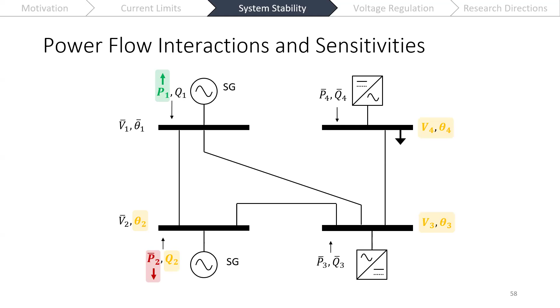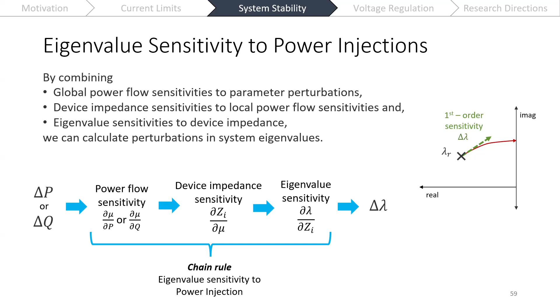What we can do then is calculate what those perturbations in our power flow would be in response to a change in the power injected at some other bus, and see how that change in our power injection results in some perturbation or change in our eigenvalues, applying the chain rule along here using the power flow sensitivities. And then if we can measure our device level impedance sensitivities to local power perturbations, and we have our eigenvalue sensitivities to changes in our equivalent device admittance, applying through this chain, we can get an idea of, for that power injection change, how much our eigenvalue is going to be perturbed.